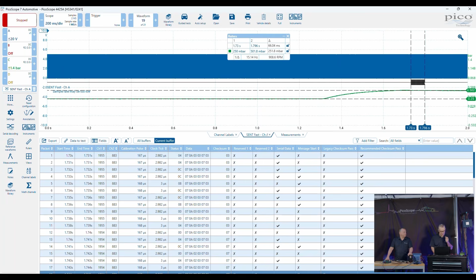1955. So what have we determined there? Well, to begin with, what we've noticed is the sensor's reacting, and it's reacting in a way that we'd imagine it would. The value has gone from a low value to a higher value with an increase in pressure. So that could be enough. We know the sensor's reacting. Is it reacting correctly?